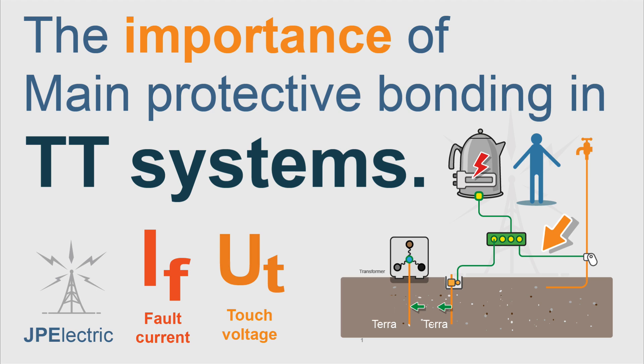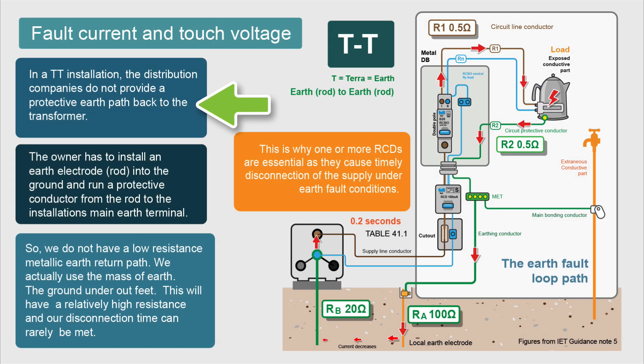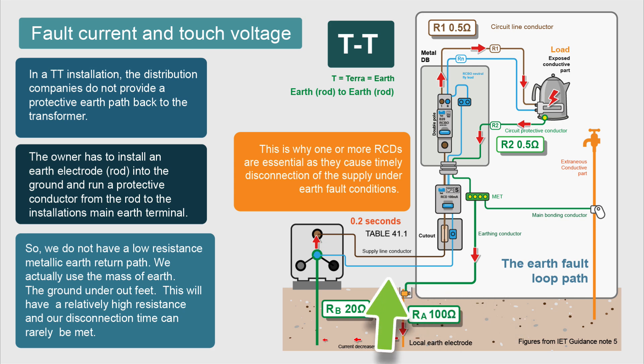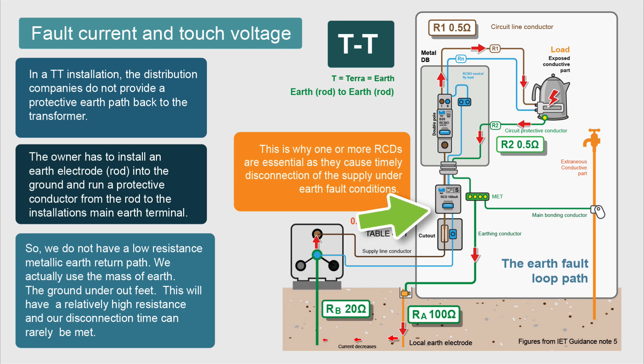Today I'm going to look at the importance of main protective bonding in TT systems. In TT installations, the distribution companies do not provide a protective earth path back to the transformer. The owner has to install their own electrode which they connect to their main earthing terminal. We don't have a low resistance metallic earth return path back to the transformer — we're using the mass of earth, and this earth return path has a higher resistance. This increases our earth fault loop impedance and disconnection times can rarely be met, which is why on TT systems it's essential that we have one or more RCDs protecting the installation, because the RCD is meeting our disconnection times.